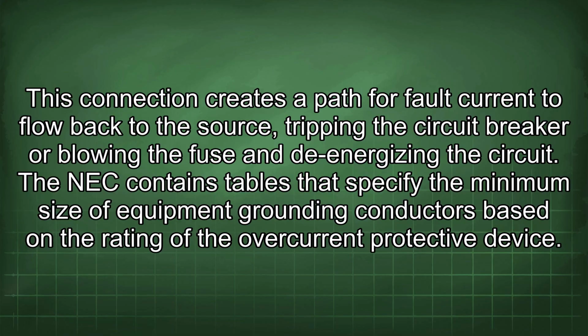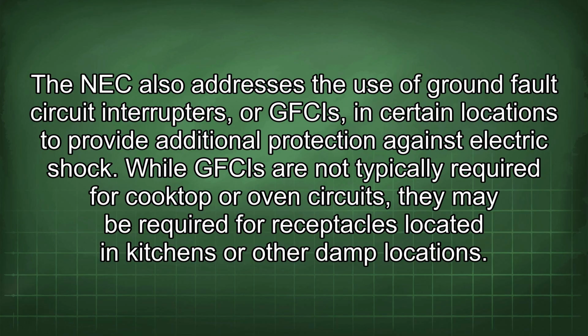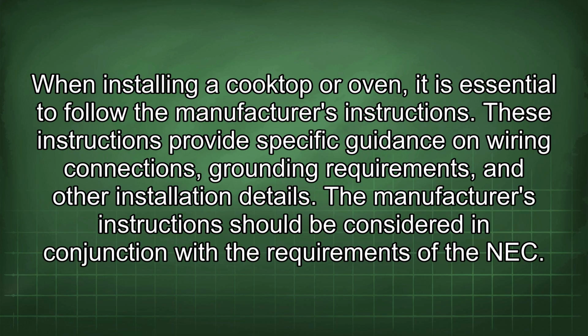The NEC contains tables that specify the minimum size of equipment grounding conductors based on the rating of the overcurrent protective device. The NEC also addresses the use of ground fault circuit interrupters, or GFCIs, in certain locations to provide additional protection against electric shock. While GFCIs are not typically required for cooktop or oven circuits, they may be required for receptacles located in kitchens or other damp locations. When installing a cooktop or oven, it is essential to follow the manufacturer's instructions. These instructions provide specific guidance on wiring connections, grounding requirements, and other installation details. The manufacturer's instructions should be considered in conjunction with the requirements of the NEC.